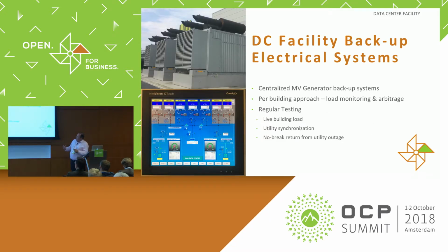Backup facilities again play into the EU Code of Conduct - we've got a centralized generator facility that's quite resilient in terms of the controls we use, with a dual redundant control system. We synchronize with the mains so we can do online testing of the generators throughout the operation of the building, and we do that regularly. Nobody even blinks an eyelid anymore - they wouldn't know whether they're on mains or generator.